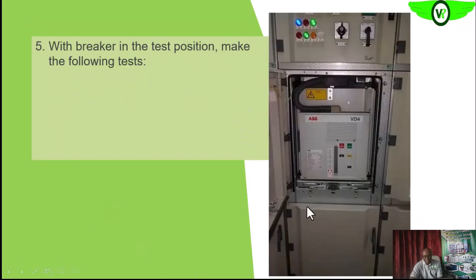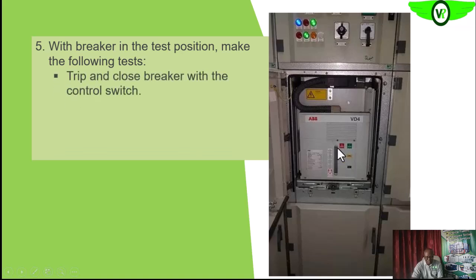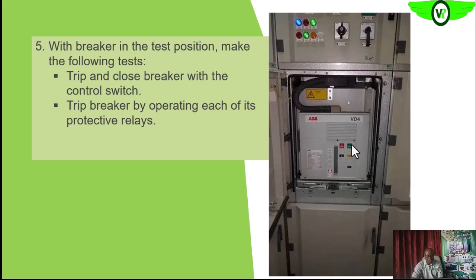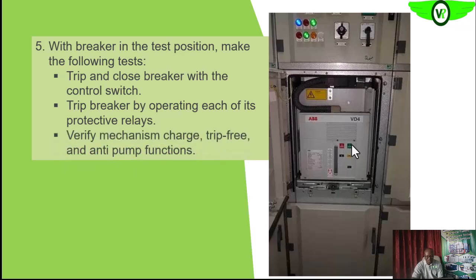With the breaker in the test position, we can carry out the following tests. We will trip and close the breaker. After racking the breaker, we can switch it off, that's the trip, and then switch it on. We should trip and close the breaker with those control buttons or switches. We'll also trip the breaker by operating each of its protective relays, which we can do by sending the appropriate signal to the protective relays. That is secondary injection, to see how the circuit breaker will respond.